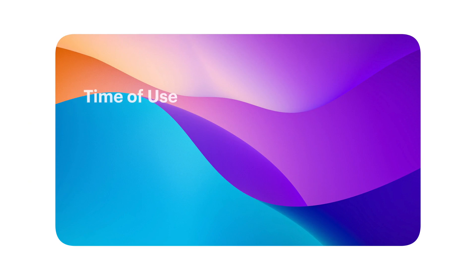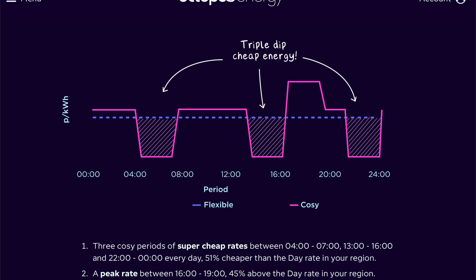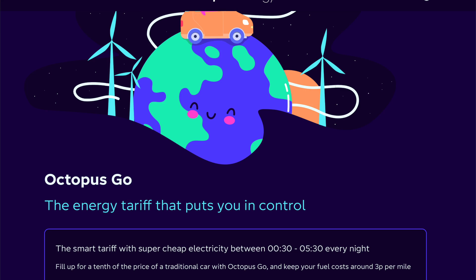The next option is time of use. Time of use and manual control would seem on the surface to do the same thing, but time of use is for people who have set time tariffs — meaning between these hours the energy is cheap and between these hours the energy is expensive. You just tell the system when your energy prices are expensive, and during the cheap hours it will import power from the grid. So if you're on a tariff like Octopus Cosy or standard Octopus Go, where you have a set defined period every single day of low cost energy, then you would use the time of use settings. Just put in when the peak times are and it will take care of the rest for you.